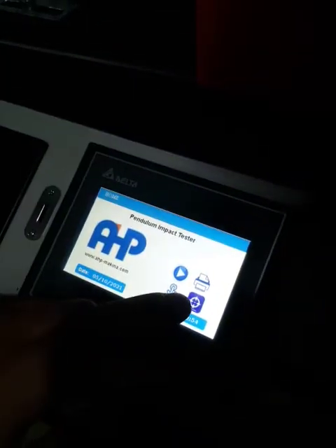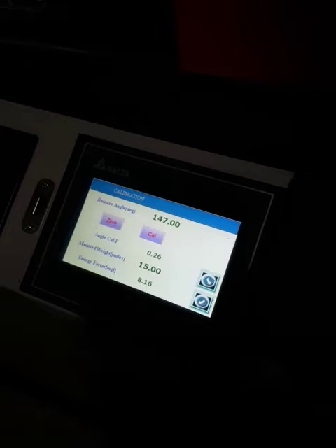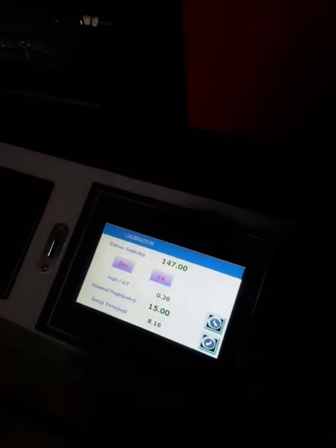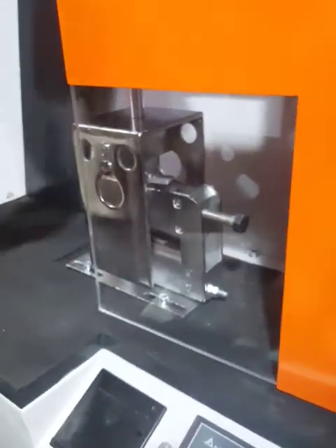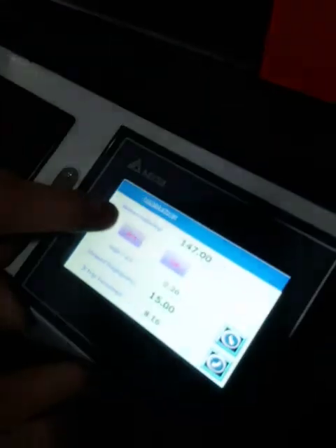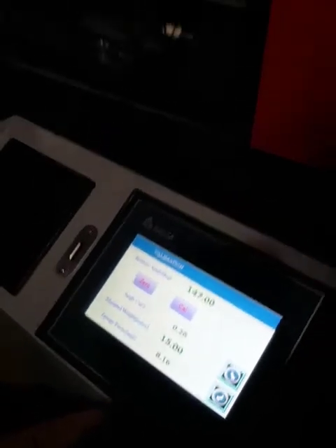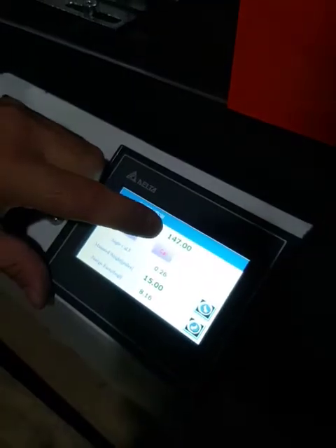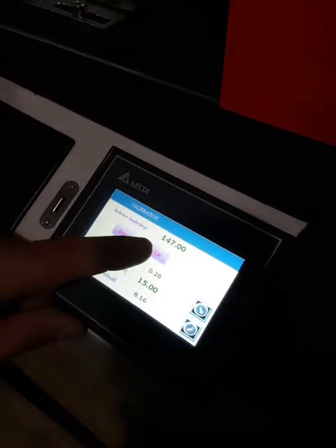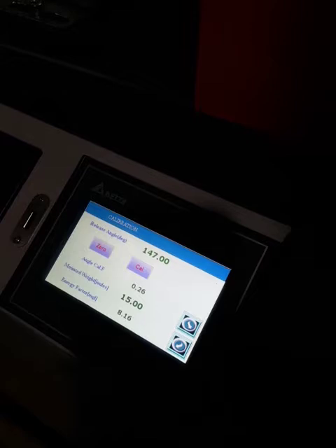Now I'm going to the software panel. On the screen we have a calibration section. At first you need to bring the pendulum down. For calibration of the machine, you need to bring the pendulum down to the zero energy point. This is a zero angle. After that, just click on zero. Then move the pendulum up, and this is the release point, and the angle of this point is 147 degrees, and click CAL as calibration.